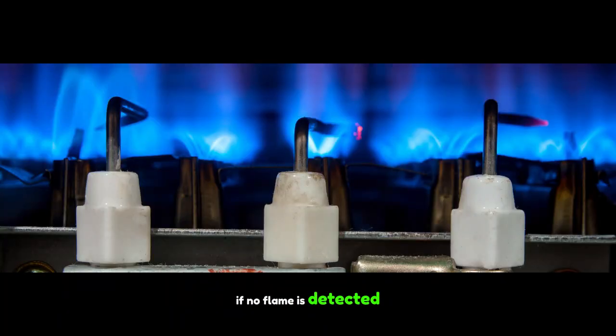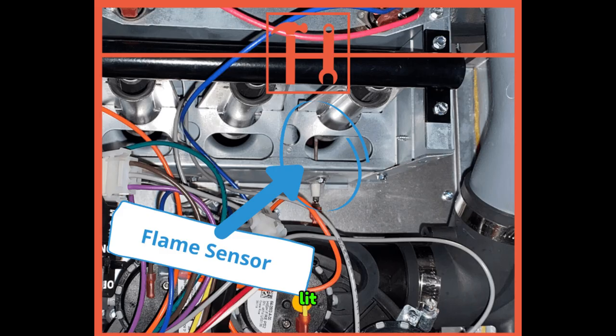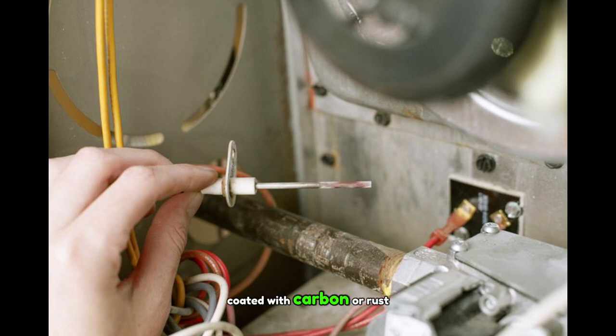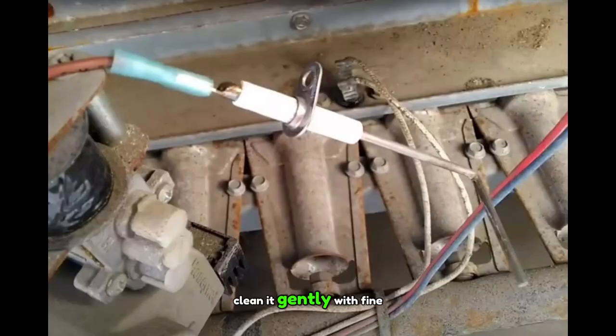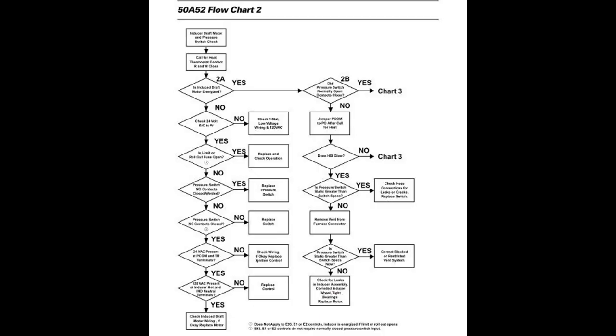If no flame is detected, even if the burners are lit, the sensor tells the board to shut down for safety. Over time, flame sensors get coated with carbon or rust, causing false flame failure signals. To fix this, remove the sensor, clean it gently with fine sandpaper or steel wool, and reinstall it. Make sure the sensor is in the correct flame path and that the ground wire is secured properly.